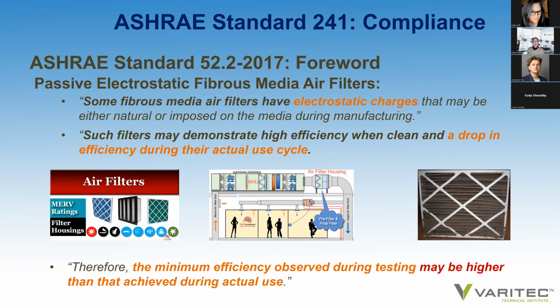In the foreword of 52.2, under passive electrostatic fibrous media air filters, ASHRAE offers this language. Some fibrous media air filters have electrostatic charges that may be either natural or imposed on the media during manufacturing. Such filters may demonstrate high efficiency when clean and a drop in efficiency during their actual use cycle. Therefore, the minimum efficiency observed during testing may be higher than that achieved during actual use.